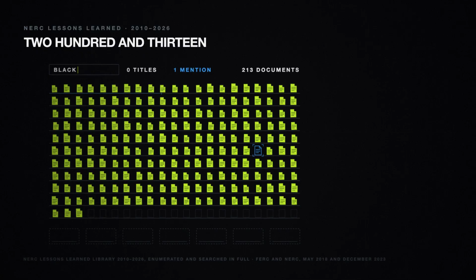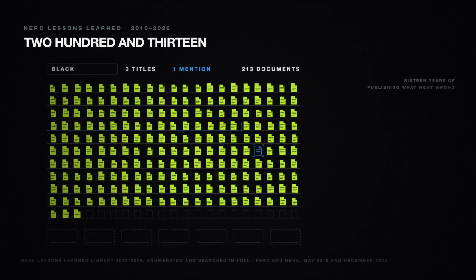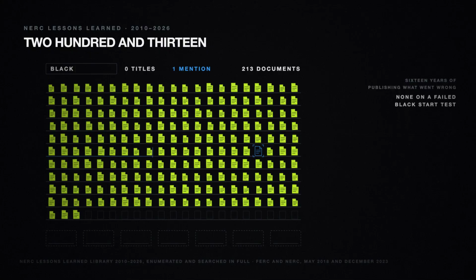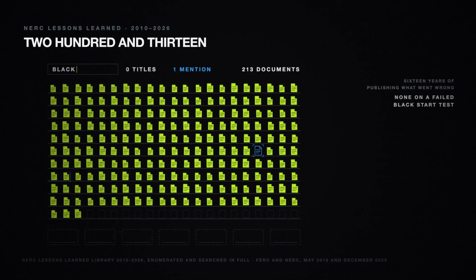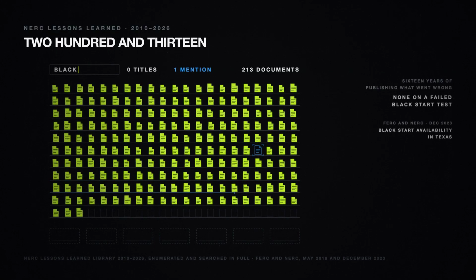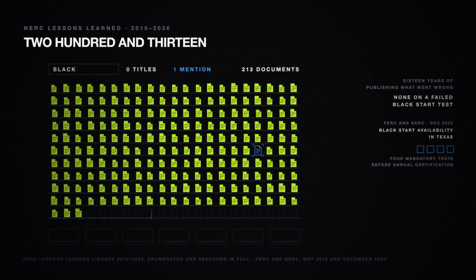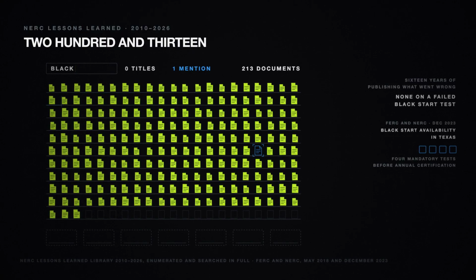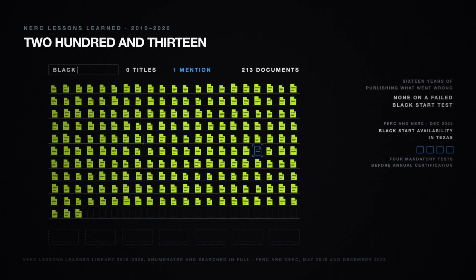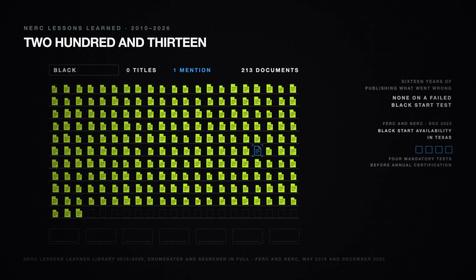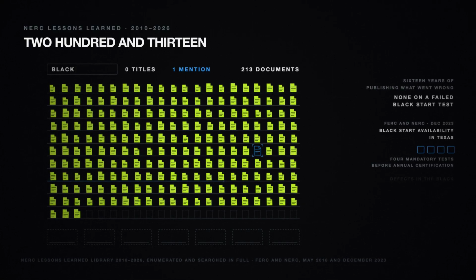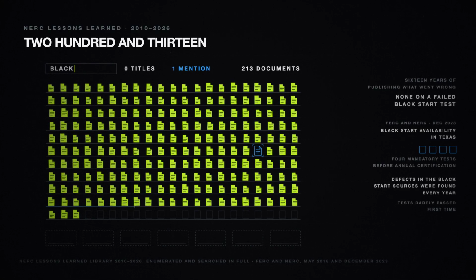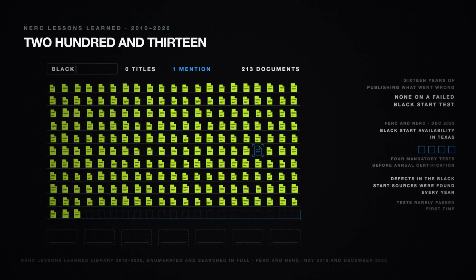Exactly 1 document out of 213 mentions black start at all, and only as a forward-looking recommendation. 16 years of publishing what went wrong, and a failed black start test has never once been the subject of one. That is not because the tests pass. In December 2023, the federal regulator and the Reliability Organization published a study of black start availability in Texas, where 4 mandatory tests are required before annual certification. Their finding: defects in the black start sources were found every year, and tests rarely passed first time.